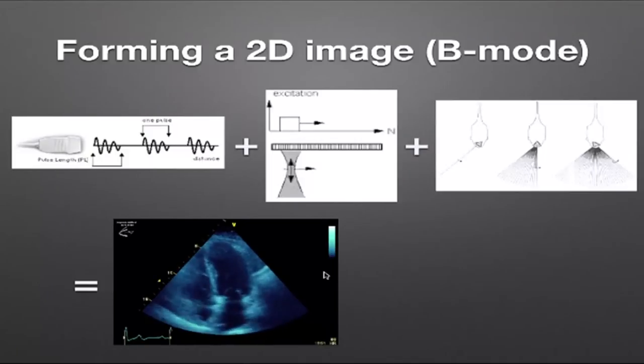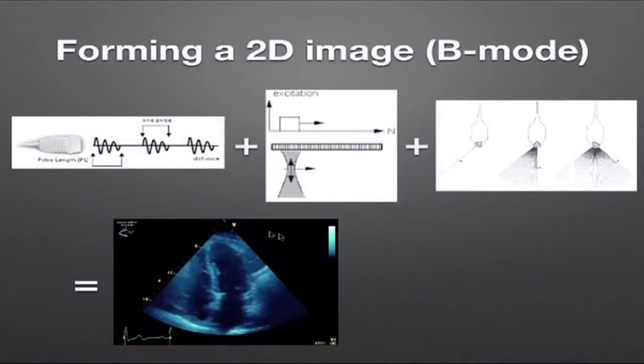This sector image is made up from many individual lines, which determines our frame rate. Sending one pulse, listening, then moving to the next section, and completing the entire sector constitutes one frame. Typically we're looking at frame rates between 40 to 80 frames per second. Our eyes naturally detect anything below about 25 frames per second as staggered, but for accurate measurements — such as the maximum diameter of the left ventricle — we want the maximum frame rate possible.